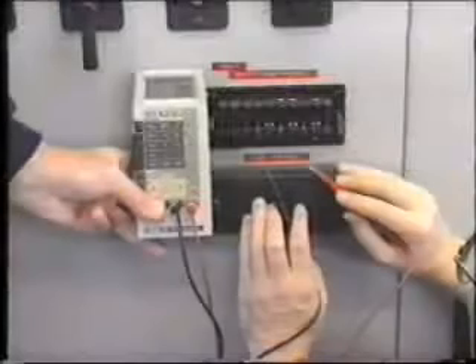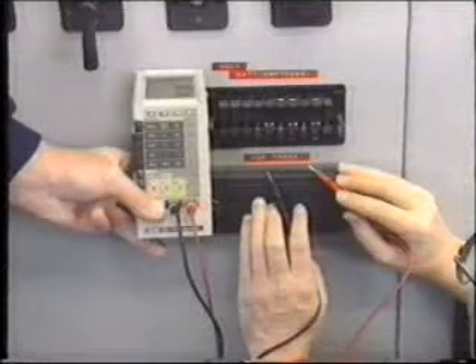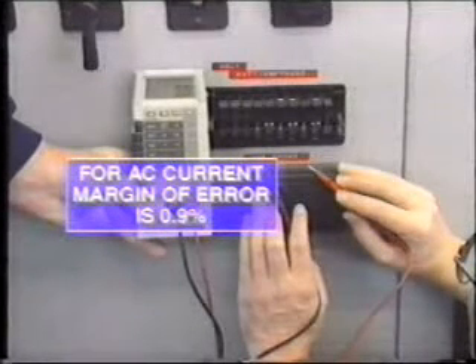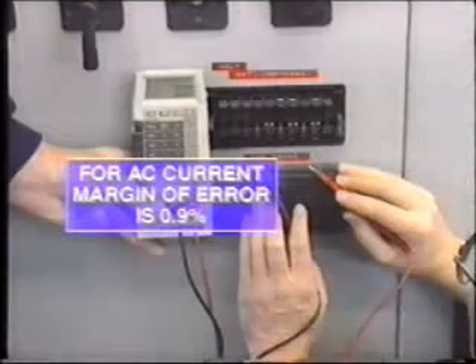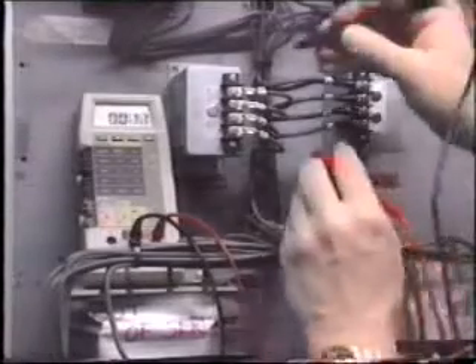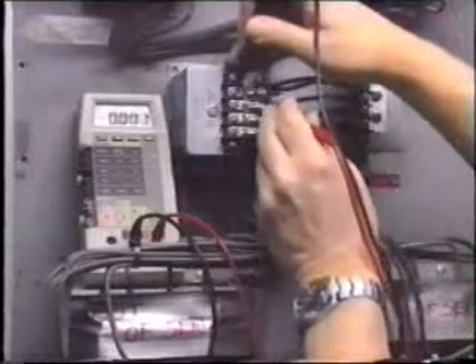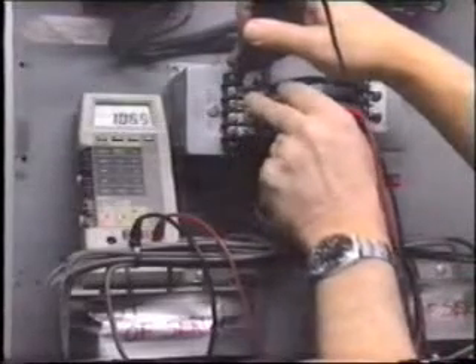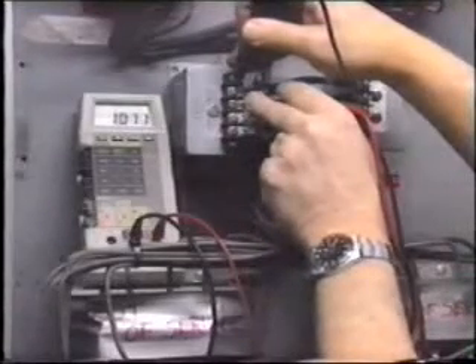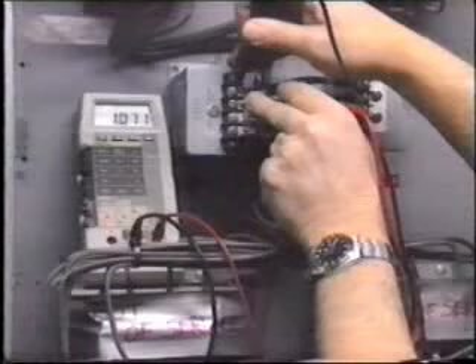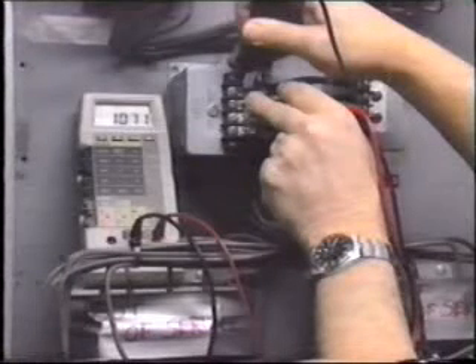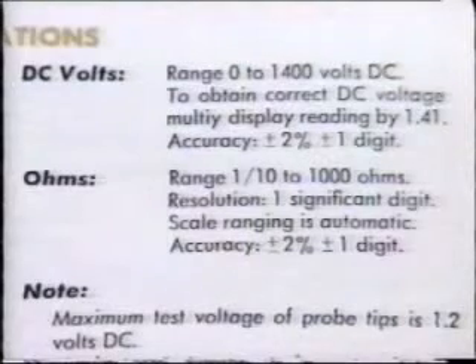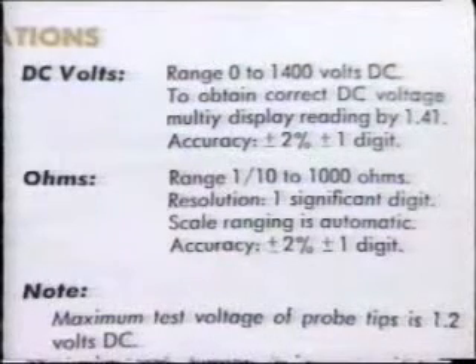Ensure that the accuracy level is suitable for the job. For example, when this digital multimeter is selected to measure AC current, we note that the margin of error is specified as 0.9%. This would not be adequate if we are, say, trying to adjust the output of a current transducer within a specified margin of 0.2%. The accuracy of adjustment can only be as good as that of the instrument which you are using for measurement. Consult the specifications when in doubt.